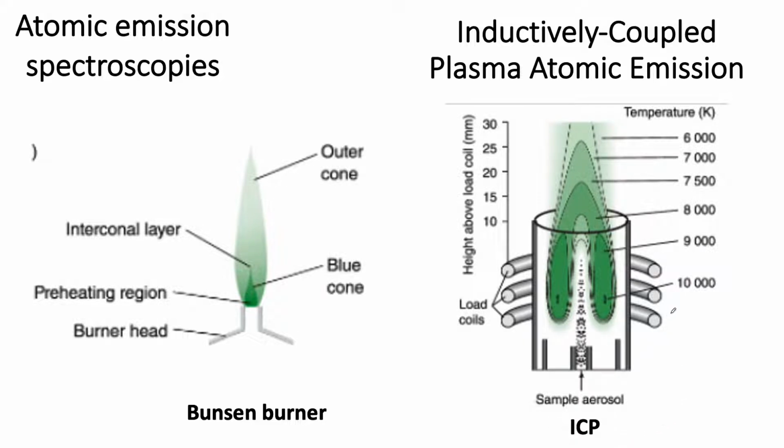And here it's showing you a coil of wire. There's a coil of wire going around where this sample is going to burn, right? The sample's coming in here. The sample is coming in as a liquid, so you have a beaker with your sample in it, whatever that is, and it's got usually metals dissolved in there, right? And you have some little pump that's sucking it out and slowly releasing it as a little spray into here, at a very constant rate, right? Because you don't want this to be a noisy situation.